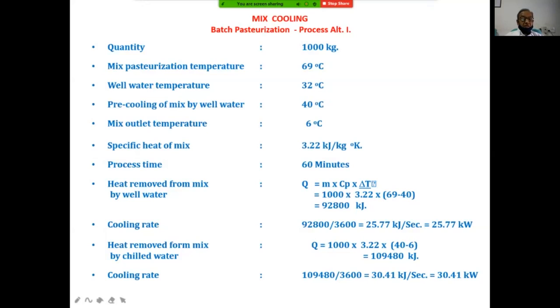Now, by chill water or the glycol solution, what is the load? It's the same 1000 kg, 3.22 is the specific heat, and the temperature difference is 40 to 6 degrees. We are getting 1,09,480 kilojoule total cooling load. And if we convert that into kilowatt, we get 30.41 kilowatt as the cooling load.